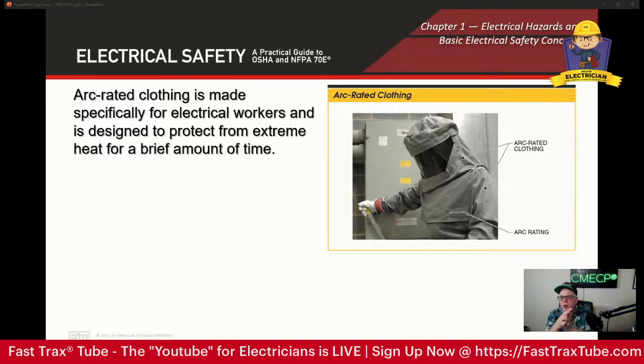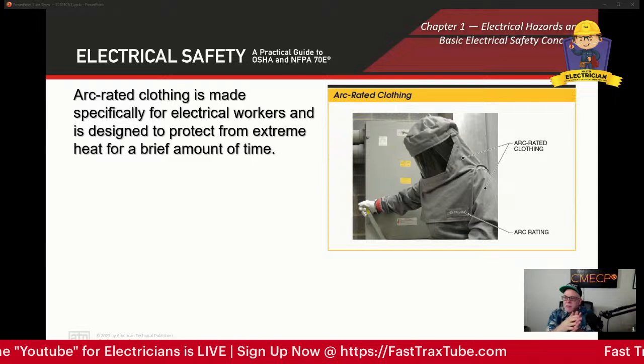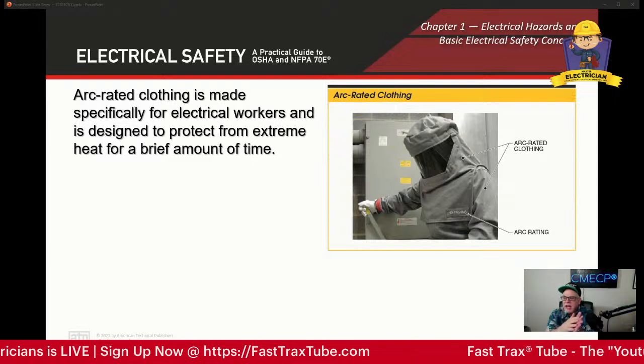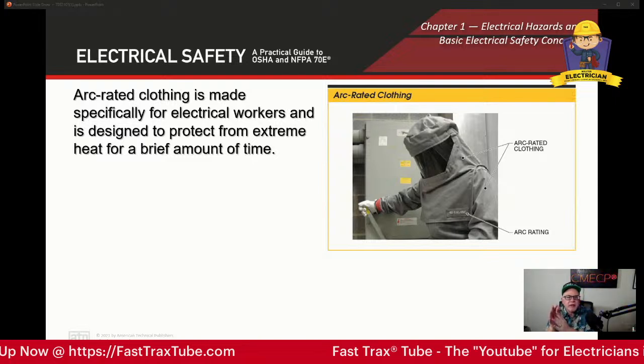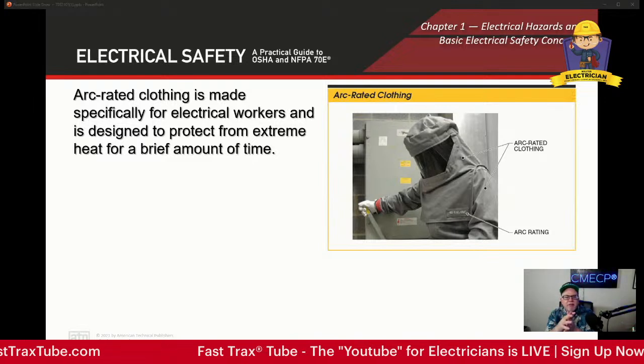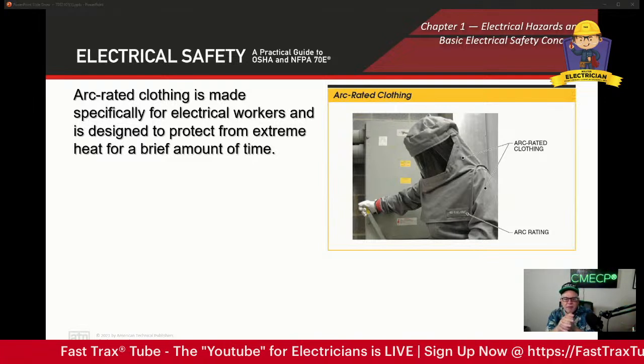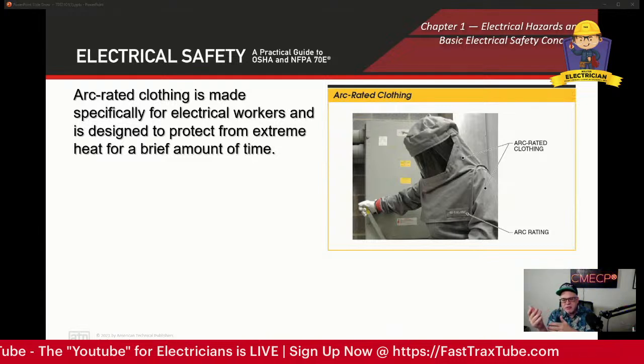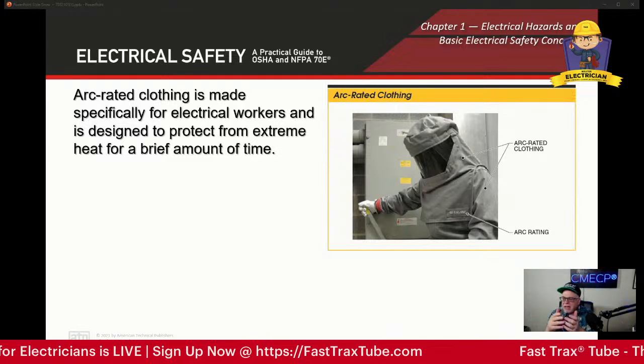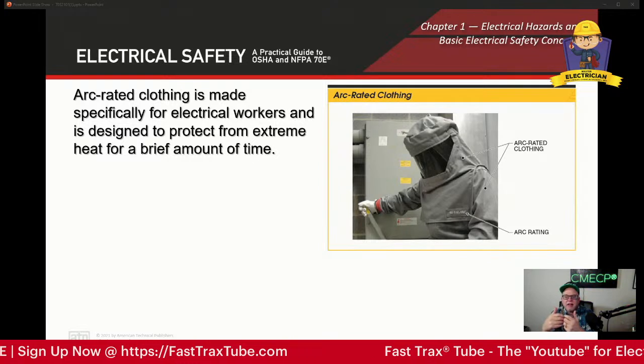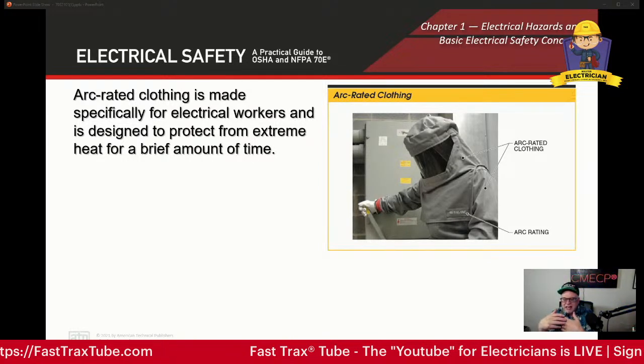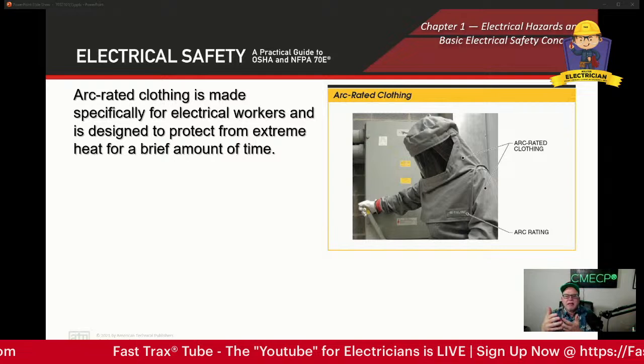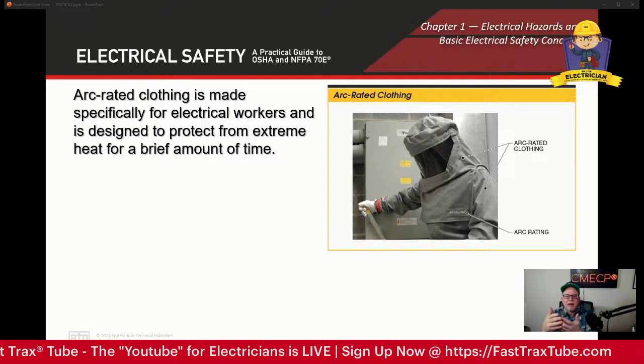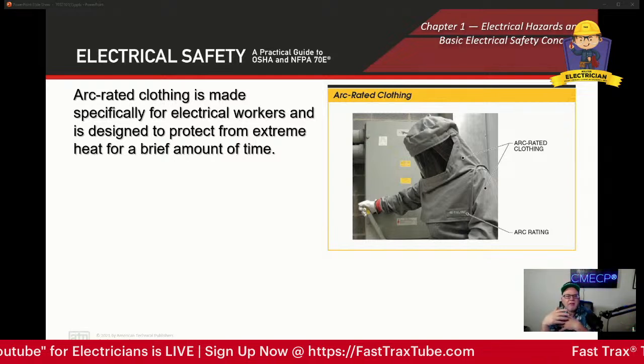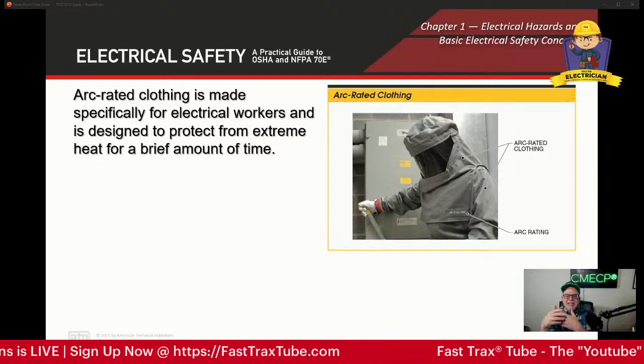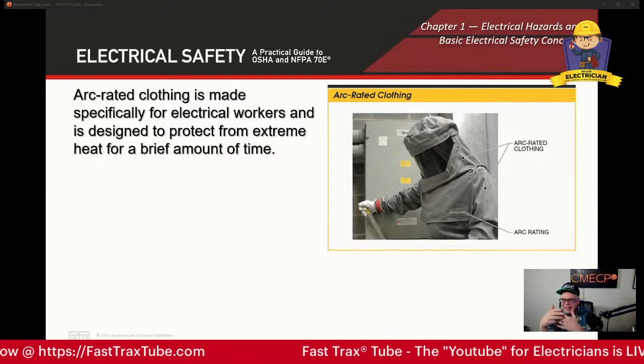Now, arc-rated clothing is made specifically for electrical workers and is designed to protect from extreme heat for a brief moment or amount of time. When we think about calorie suits and the different calorie ratings they're made in, they're designed to handle the incident energy immediately. When we have an arc rating, we're concerned about the amount of energy exposed, the heat that comes out from that incident.